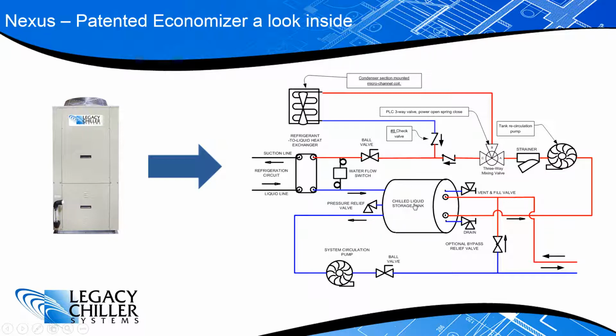Now, as I mentioned before, when there's a call for cooling, the PLC, on an economizer-enabled chiller, will take a look at the tank temperature at the time of the cooling call, and it's going to look at the outdoor ambient temperature. So if it sees about a 10-degree differential minimum, it's going to go ahead and energize this three-way mixing valve and make a connection between A and B. So it's going to force this fluid out, and basically this is the microchannel coil that we looked at a few minutes ago. It's going to put that in series. It's going to come through here with the evaporator and then back to the tank. So this is a normal flow pattern for economizer.